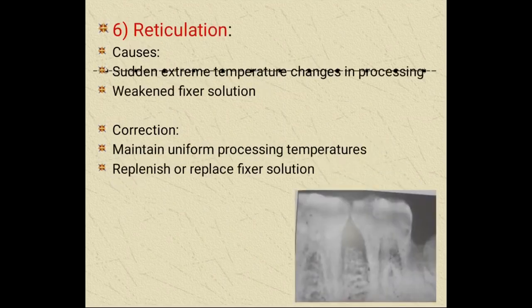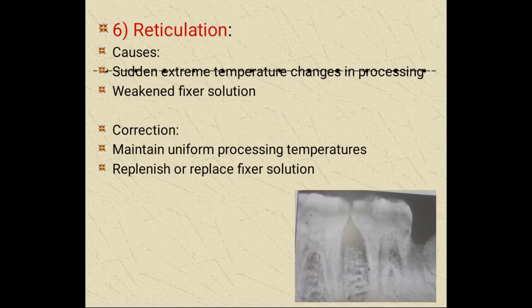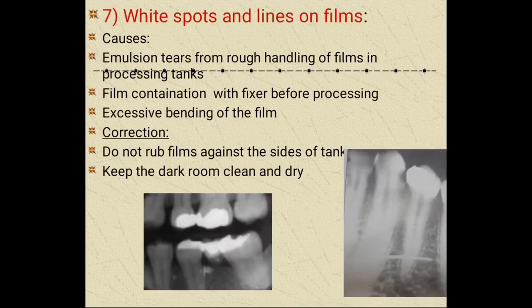Reticulation shows a reticulate appearance, due to sudden extreme temperature changes in processing. Correct by maintaining uniform processing temperature and replenishing or replacing the fixer solution. White spots and lines on the film are due to emulsion tears from rough handling of film in processing tanks, film contamination with fixer before processing, or excessive bending of the film. Correct by not rubbing the film against the side of the tank and keeping the dark room clean and dry.